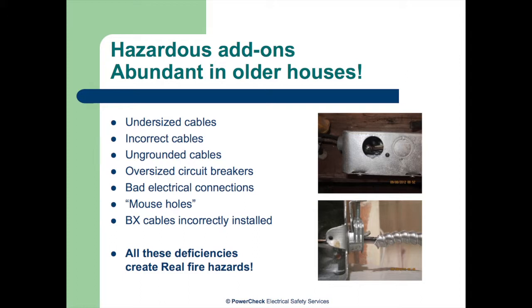Anyway, let's run through some fire hazards really quick. This is the kind of stuff we see: undersized cables, incorrect cables, ungrounded cables, oversized circuit breakers, bad electrical connections. We call them mouse holes. They're actually called knockouts, those holes, but mice go into those holes and build nests, and then you have fire. It takes 25 cents to buy a little cap that snaps on and seals it up, and then you don't have problems. So many houses burnt to the ground because of mice and spiders and stuff going into the electrical boxes because of mouse holes. It can be fixed so easily.